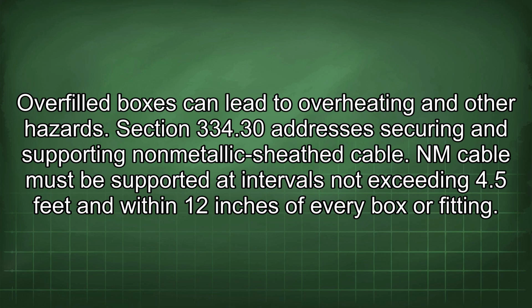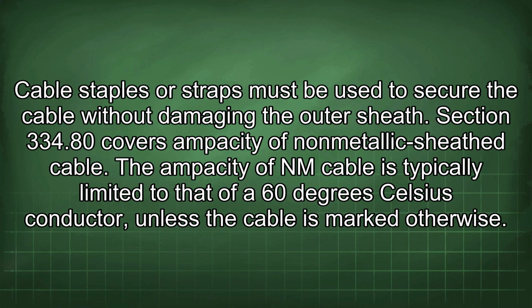Section 334.30 addresses securing and supporting non-metallic sheath cable. NM cable must be supported at intervals not exceeding 4.5 feet and within 12 inches of every box or fitting. Cable staples or straps must be used to secure the cable without damaging the outer sheath.